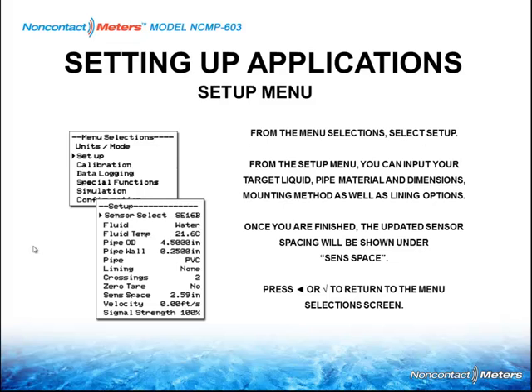And in addition to that, you'd also have to take into account if you had a mixture, say water and glycol there. So keep that in mind. We may have to calculate the sound speeds if you have a ratio of certain glycol and certain water and so on. Fluid temperature, you pop in there, pipe OD. Pipe outside diameter is the most common mistake that people put in.